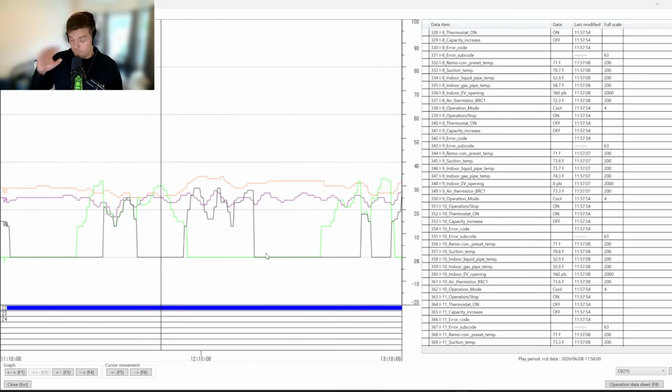But also, there's more to this video, obviously, even though I wanted to end it a while ago. There's more to this because when we talk about small instances like this, if my system is applied incorrectly, application matters. When I say applied incorrectly, that just means that the space this serves never has a real heat demand, never has a real heat load. The way they're using this office isn't the way it was originally designed. Maybe the DOAS system has changed. Maybe someone changed the discharge set point on the DOAS for the air that's coming into the return air of these units, that's derating the coils.